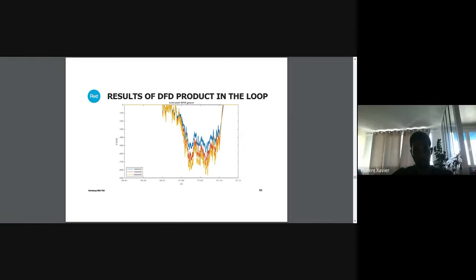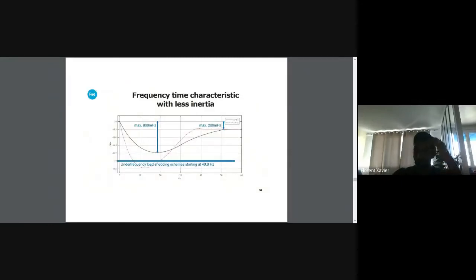Next, we speak about the inertia reduction. There are two parts on that: one on the inertia reduction and the impact on the system, and the last is about grid forming. This simulation is based on the policy one that I explained before. It's a system with a generation unit of 150 gigawatts with an inertia constant of 5 seconds, and we simulate the loss of two units, so a 3 gigawatt loss.